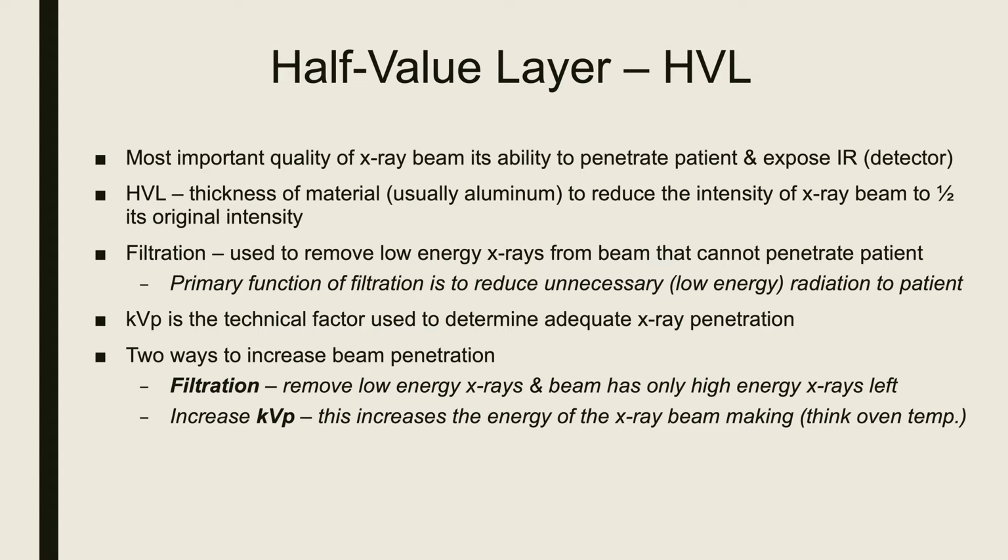So there are two ways you can increase the beam penetration. You can either increase the kVp, which is what we usually do, or you can increase the amount of filtration, and that will remove all the low energy X-ray beams, and you'll just have high energy X-rays left.